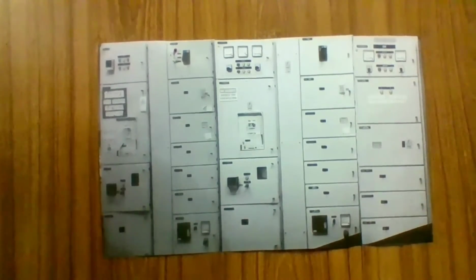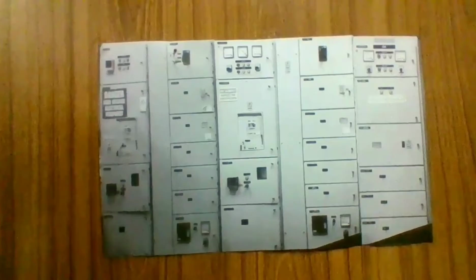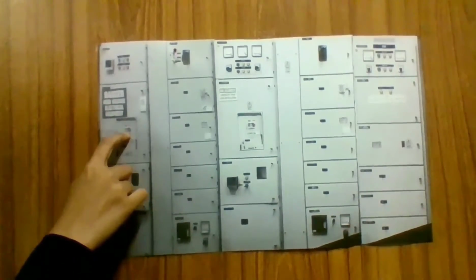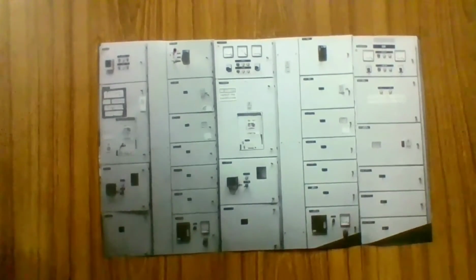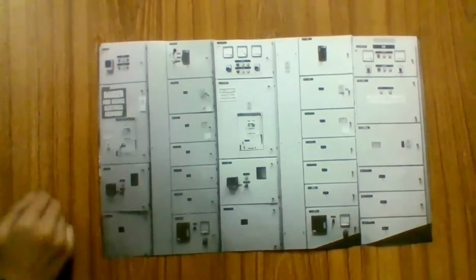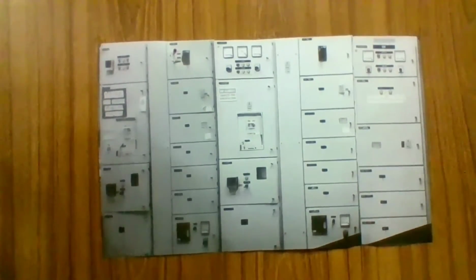Next, turn off the ACB by pushing the red button until it changes to green color. Next, check the busbar supply indicator. It should show the off state, showing that the busbar has been de-energized. Next, turn off the incoming power supply of MSB1. The MSB1 is now fully de-energized.